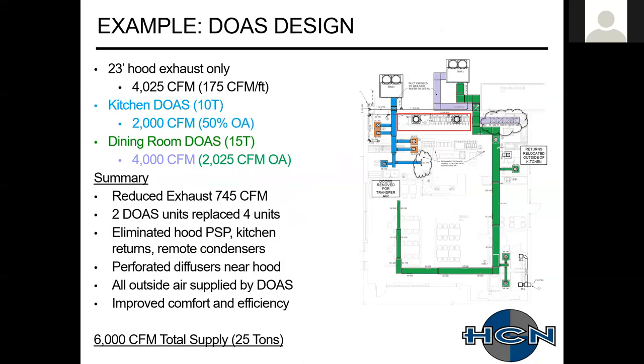They did a redesign on it, opened it up. They were able to eliminate the air handlers up front, go with two dedicated outdoor air units, return for the one side. I think it was a 50-50 split on this one. Let me get my laser pointer out. And then a dedicated outdoor air unit that would serve for the makeup air for the hood system itself. They're able to lower the exhaust rate of the hood. The hood's performing properly at that lower exhaust rate with a proper capture and containment test that was done in commissioning. So they were able to reduce the air required. CFM went down, tonnage went up a little bit, but the overall cost of the system was pretty much in line with the standard system, and this provided a more comfortable environment for everybody.